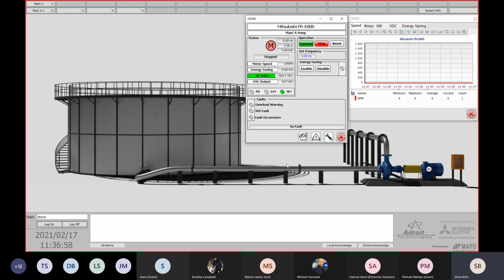Now, I just quickly want to pull up my SCADA here. So basically, what I've done here, I'm using our Adroit SCADA, connecting to a VFD over Modbus TCP communication. So there's no PLC in between. I'm communicating directly with the drive. I've designed a faceplate where I can stop and start the drive and also monitor my hertz, my amps, the kilowatt, the motor speed, my energy saving. I'm also monitoring the DC voltage and the output voltage, which I want to show you guys that changes when I enable the energy saving.